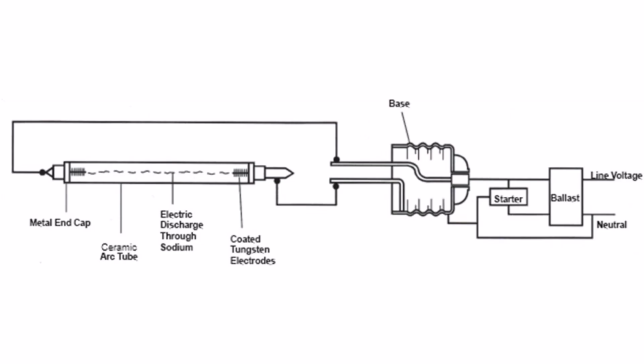Sometimes a streetlight isn't working because of two separate problems. This can be really confusing. For example, let's say a light fixture has a loose power connection — problem 1 — and a tiny arc caused by that loose connection also broke the lamp starter circuit — problem 2. If you just put a new, good HPS lamp into this fixture, it won't light up, and you'll be scratching your head why.